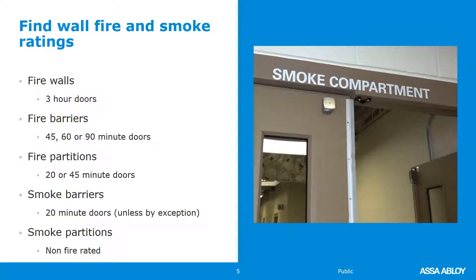Smoke barriers will be a one-hour wall with 20-minute doors unless by exception. Smoke partitions are non-fire rated. Some, based on the occupancy, will have exceptions — you may have smoke barriers in a hospital that do not require positive latching, or doors in a smoke barrier that do not require a door closer, and possibly no fire rating at all. That's why it's important to know the occupancy type and use all of this information together.